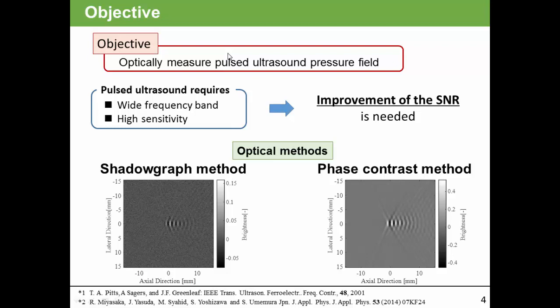The optical method for ultrasound field can be classified to two categories. One is shadowgraph method. The other is phase contrast method. For a pulse ultrasound pressure field in this study, phase contrast method has high SNR. So, we selected phase contrast method for measurement of pulsed ultrasound field.